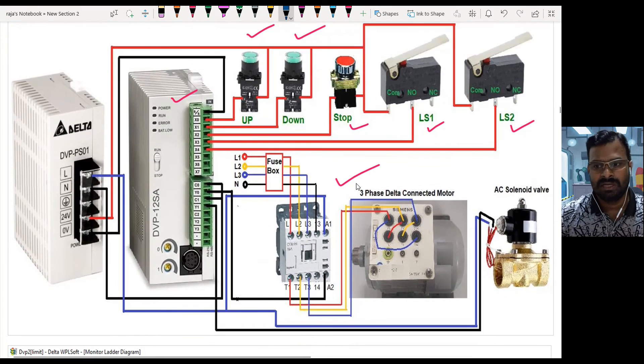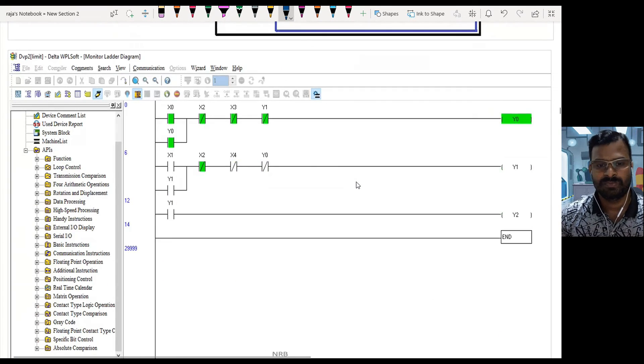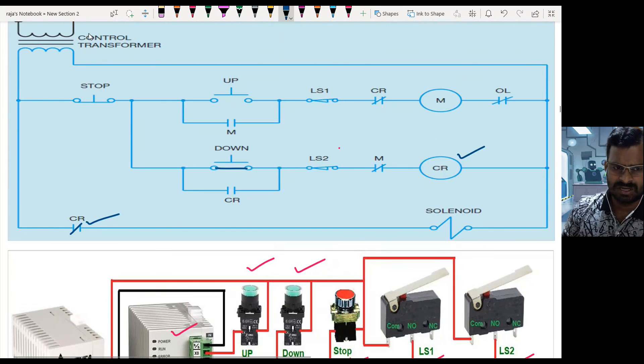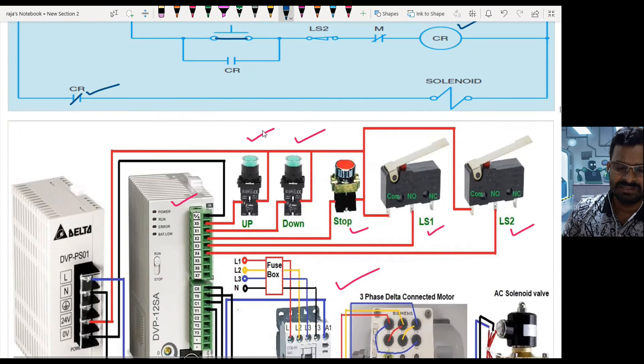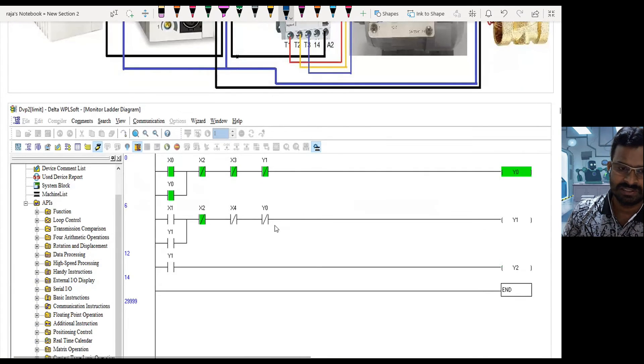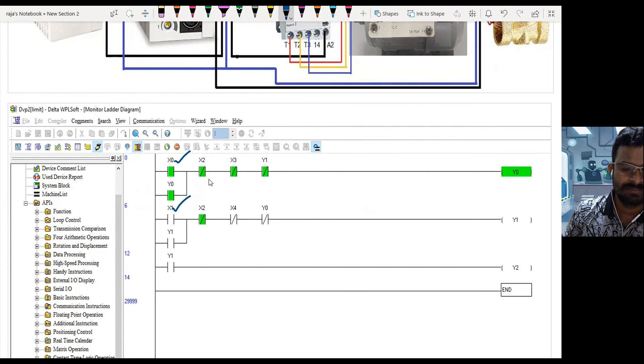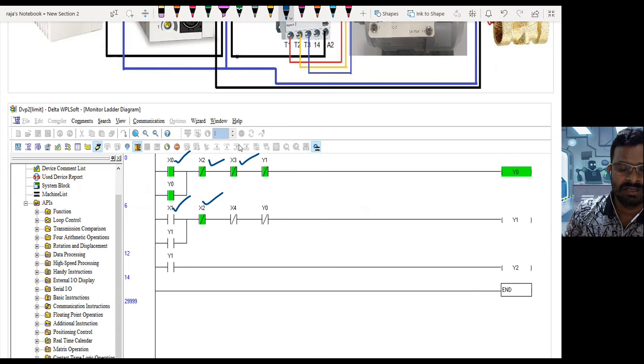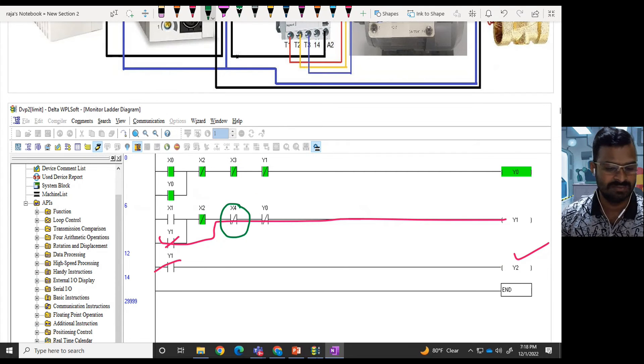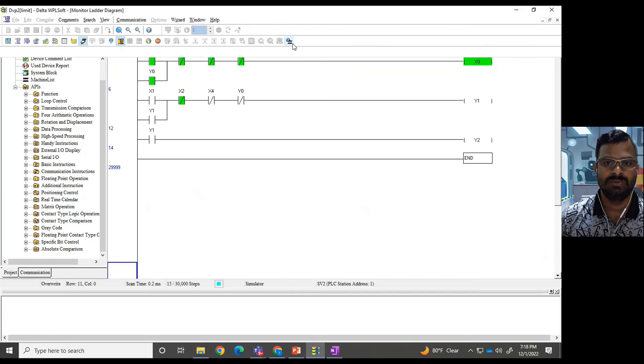This is the wiring diagram. Let us see the ladder logic code. The control circuit I drew is converted into ladder logic. I have X0 for the up push button, X1 for the down push button, X2 for turning off the total process, X3 for the upper position limit switch, and X4 for the lower position limit switch. Let us simulate it.